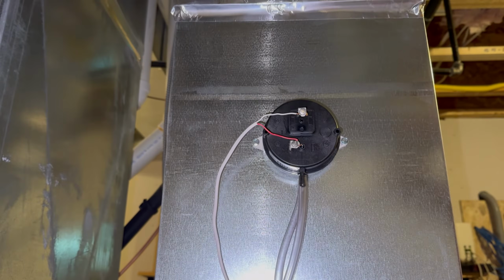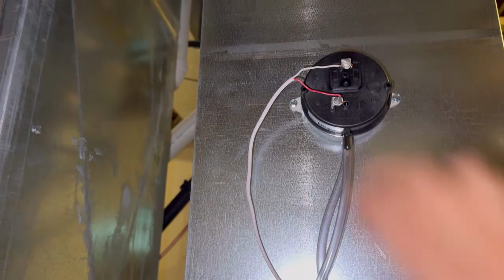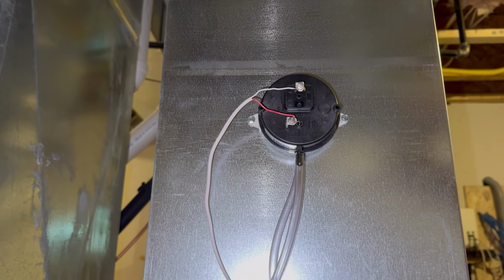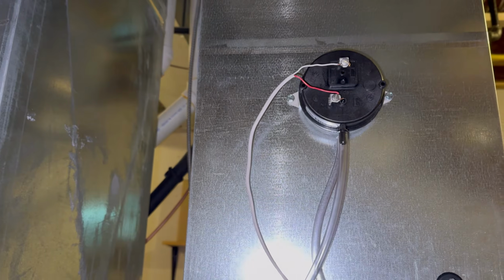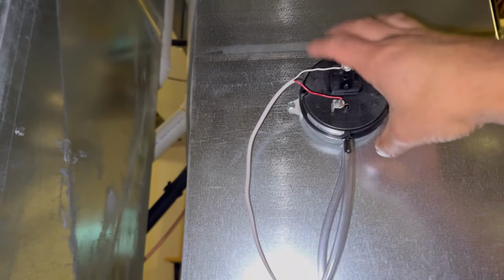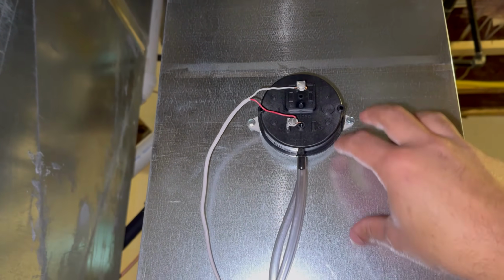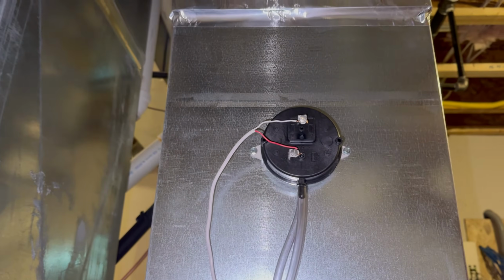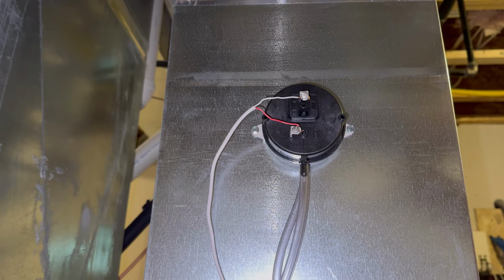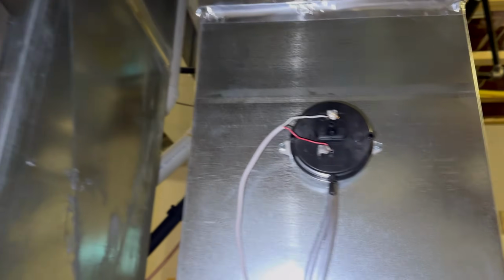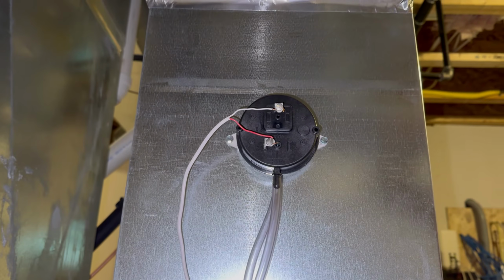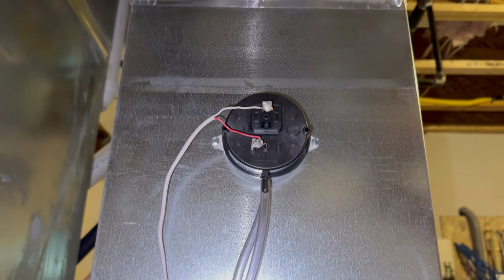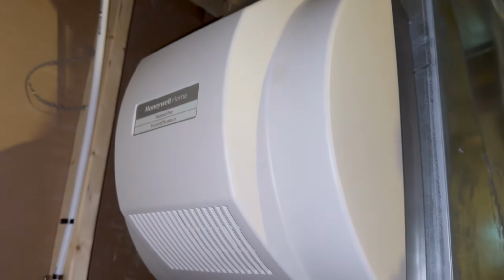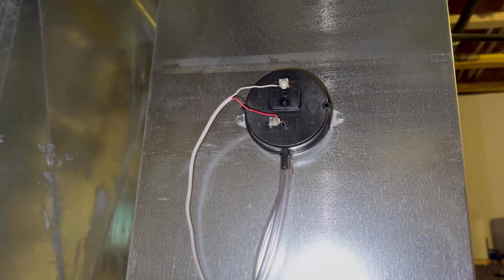that this can run. For those of you feeling adventurous and don't want to use a pressure switch and you want to wire this directly to your furnace control board, you need to understand one thing, and I'll also show you how to wire it. What you need to understand is that this pressure switch allows you to run the humidifier anytime airflow is present in the ductwork, which means it doesn't mean you need to have heat on. You could be running your circulating fan and still use your humidifier. But if you connect this to your furnace control board, I'm going to show you how to connect it so that only when the furnace is heating will this humidifier turn on. So if you're okay with that, I'm going to show you how to wire this directly to your control board.